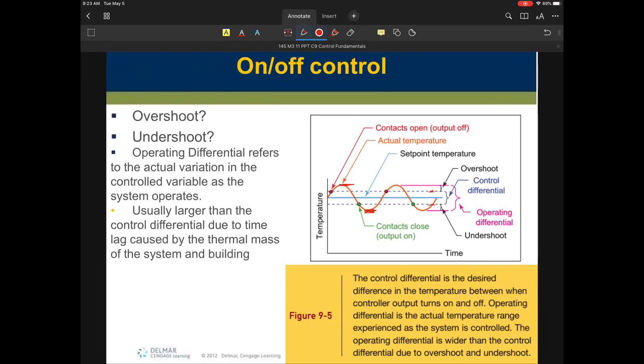This is something that you have to be aware of a little bit in control systems, and that's one of the reasons why boiler temperature control is so significant, depending on the types of emitters that you have. So if I have really low mass heat emitters, it's less likely that I would end up doing this major overshooting. The higher the mass they are, the more I have to recognize and understand the control of that. So just a little bit on that.